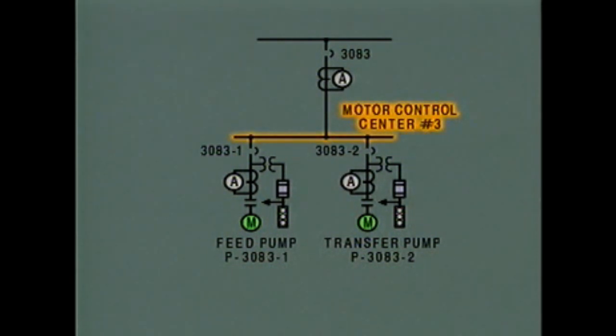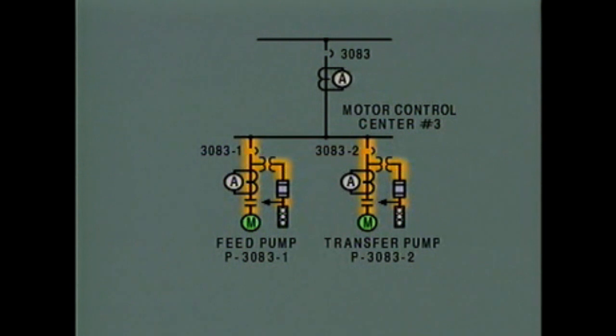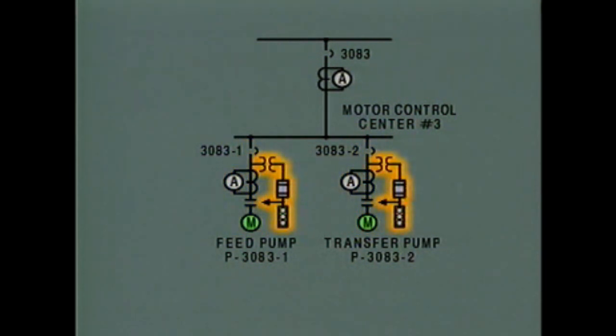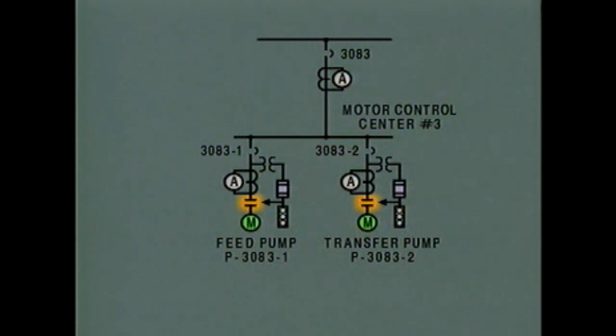Power then flows to the motor control center. A motor control center is basically a bus that supplies power only to motors. This motor control center includes two identical motor circuits. Each motor circuit includes a power circuit and a control circuit. In each power circuit, power flows through a circuit breaker and a current transformer, then to a motor contactor.